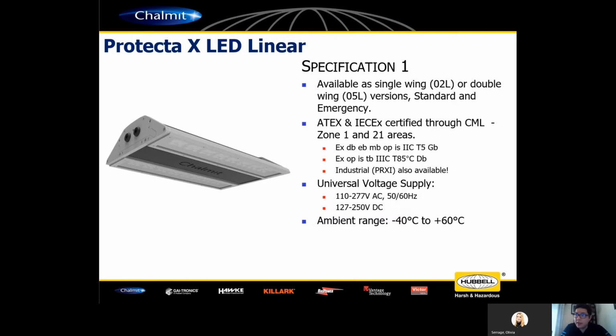The product is fully certified for both ATEX and IECEx areas for Zone 1 and 21. We've essentially ticked off every letter of the alphabet in the coding, but bear in mind the luminaire is an EXE product. That means we can have a lighter, more compact solution for Zone 1. EXD luminaires tend to be a bit more heavy and robust, to contain an explosion essentially, whereas EXE eliminates that from happening.